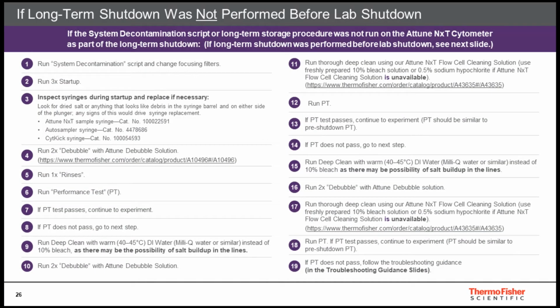Now that we have reviewed all the materials and procedures needed, let's talk about restarting the Attune NxT if the Attune NxT was not placed in long-term storage. The long-term storage procedure involves running the first two phases of the system decontamination script, and the instrument, after rinsing out with DI water, is left dry. Alternatively, a procedure where the system is left free of salt and dry is an ideal state for the Attune NxT for long periods of inactivity. If the Attune NxT did not go through a long-term shutdown procedure, start by running the system decontamination script, because this is the best script to run in order to decontaminate the instrument.